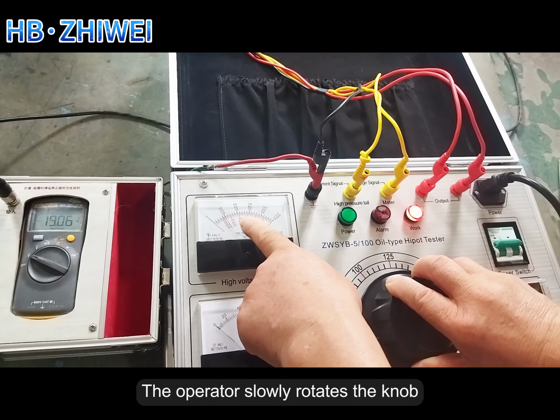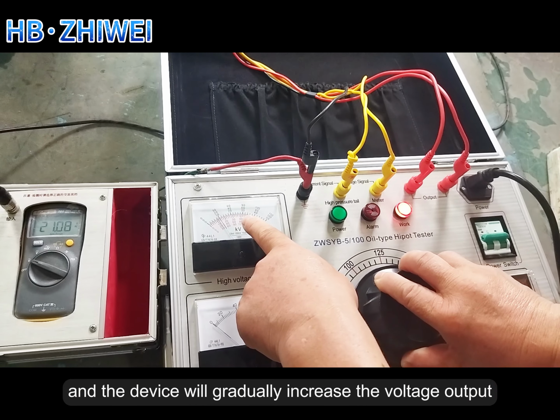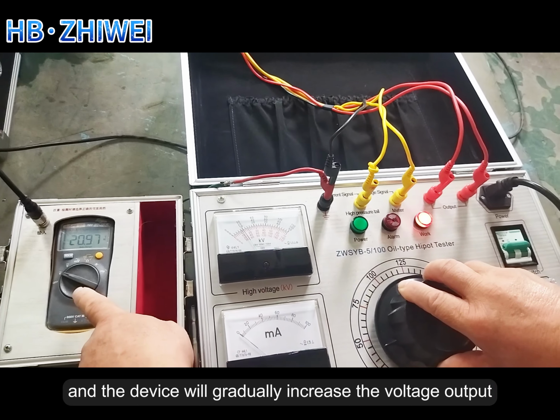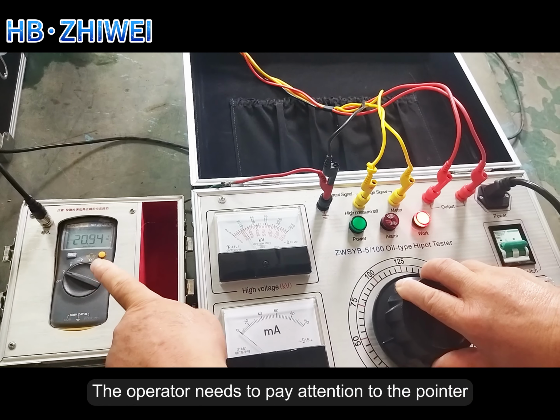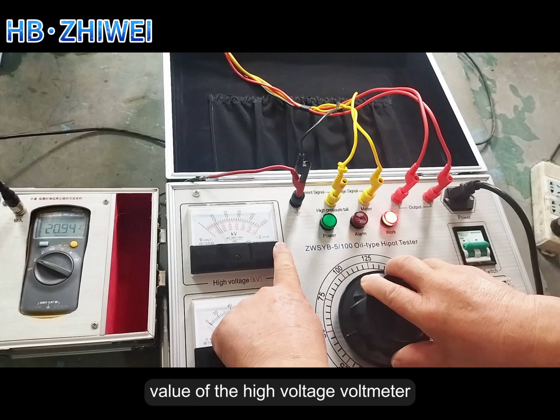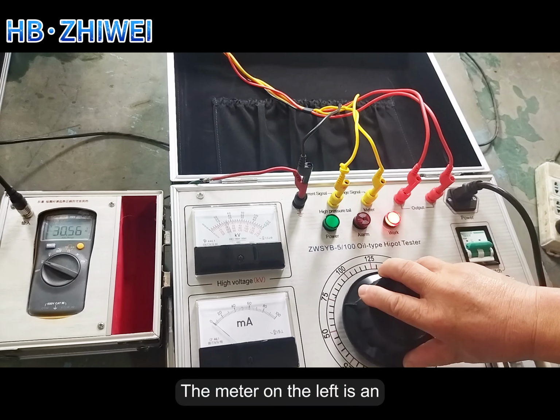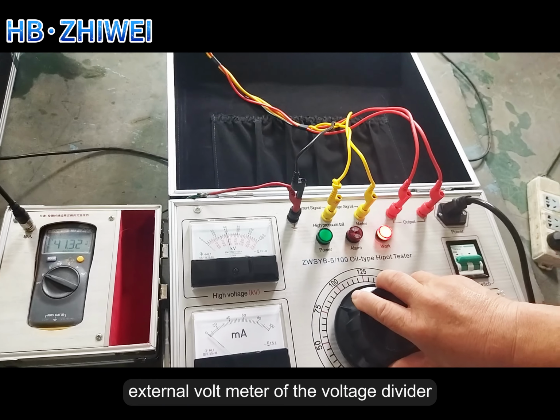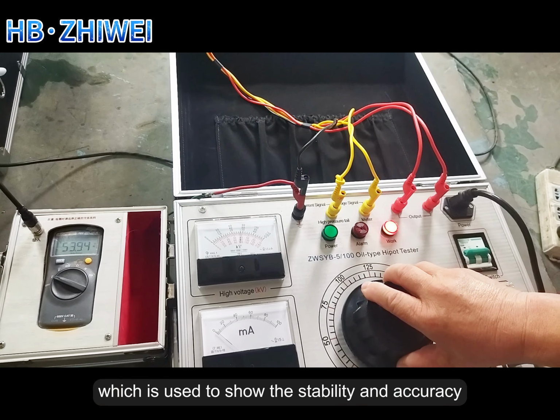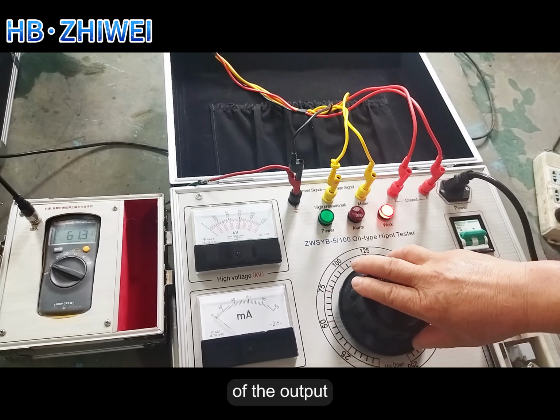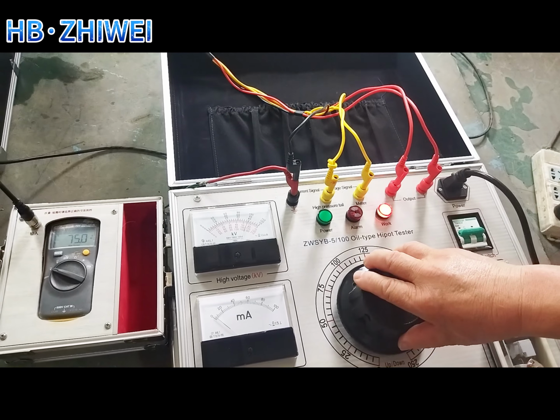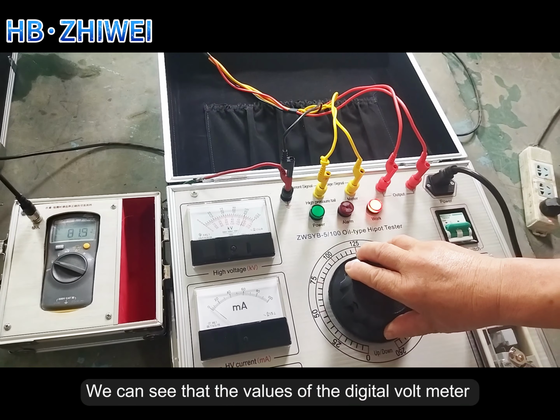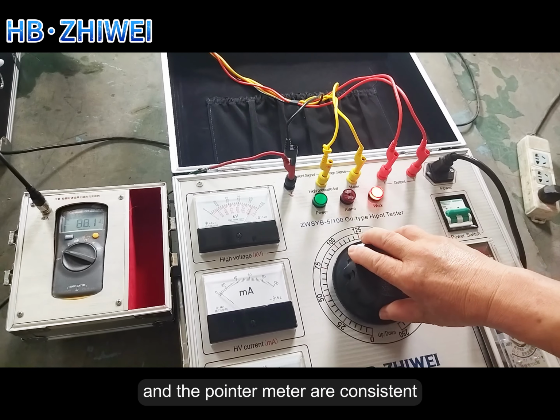The operator slowly rotates the knob, and the device will gradually increase the voltage output. The operator needs to pay attention to the pointer value of the high voltage voltmeter. The meter on the left is an external voltmeter of the voltage divider, which is used to show the stability and accuracy of the output voltage of this device. We can see that the values of the digital voltmeter and the pointer meter are consistent.